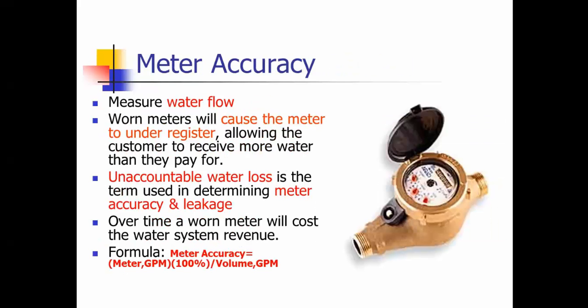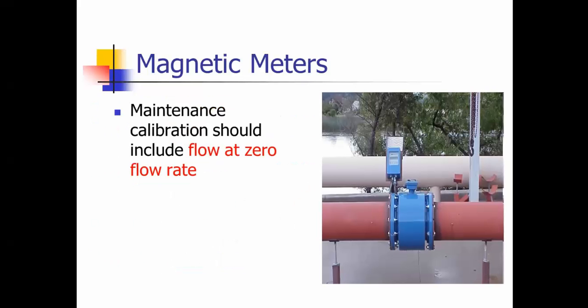Meter accuracy. Measure the water flow. Worn meters will cause the meter to under-register, which will give your customer pretty much free water, and so you want to make sure you test those periodically. There's a lot of unaccountable water loss to worn out meters, and over time it's going to cost you in revenue. This is the formula for meter accuracy at the bottom. Mag meters or maintenance calibration should include the flow at zero, flow rate.